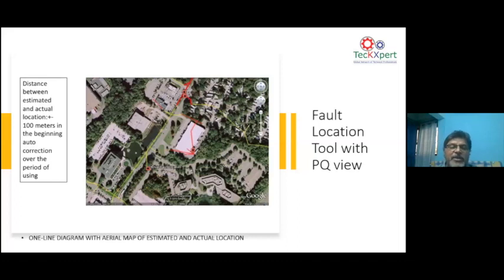That means if you have an underground cable or an overhead line, by using this continuous PQ monitoring, you can see on a Google map exactly where the fault has taken place. Fundamentally, when a disturbance or a fault happens, the moment the fault happens your breaker will trip, and the protection relay will know the cause of the trip, and your PQ meter would already have captured the pre-fault and during-fault waveforms. That means with the protection relay data, the breaker trip data, and the waveform data, the software will compute the distance to fault, and also look at the resistance to fault.